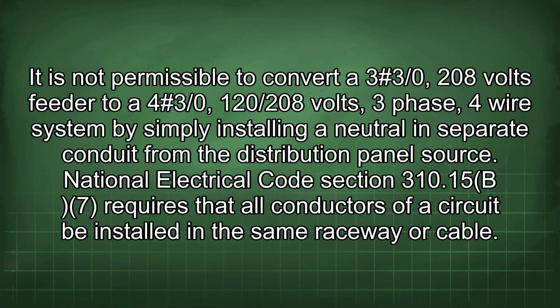It is not permissible to convert a 3#3/0 208 volts feeder to a 4#3/0 120/208 volts 3-phase 4-wire system by simply installing a neutral in separate conduit from the distribution panel source. National Electrical Code Section 310.15(B)(7) requires that all conductors of a circuit be installed in the same raceway or cable.